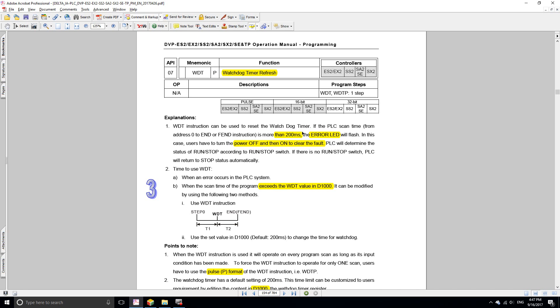If you know that you're going to spend more than 200 milliseconds on one scan cycle, you can use this function to reset the watchdog timer back to zero. Let's say this is the first step, less than 200 milliseconds. You refresh the watchdog timer, then you have another 200 milliseconds until you reach the end of your cycle.